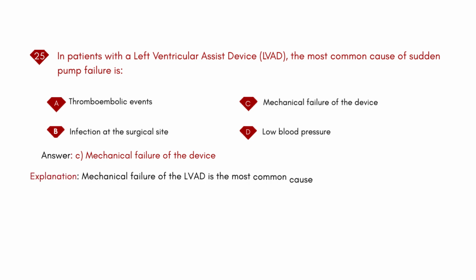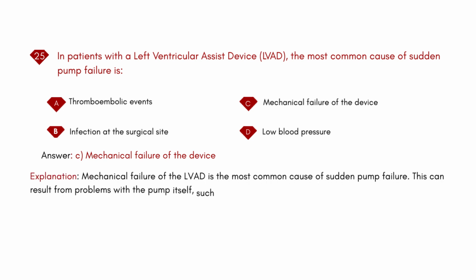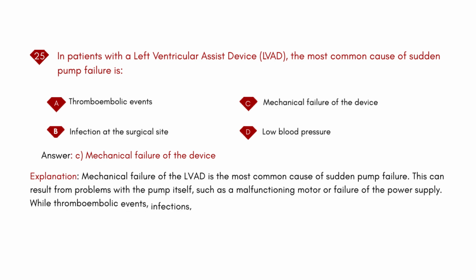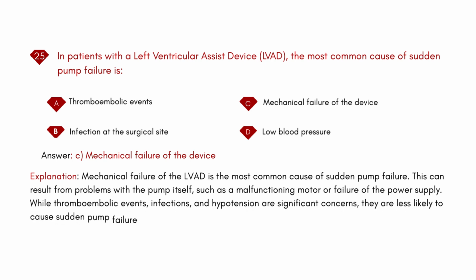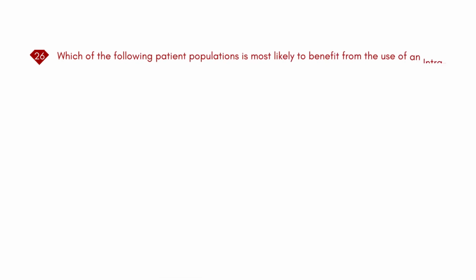Explanation: mechanical failure of the LVAD is the most common cause of sudden pump failure. This can result from problems with the pump itself, such as a malfunctioning motor or failure of the power supply. While thromboembolic events, infections, and hypotension are significant concerns, they are less likely to cause sudden pump failure compared to mechanical issues.